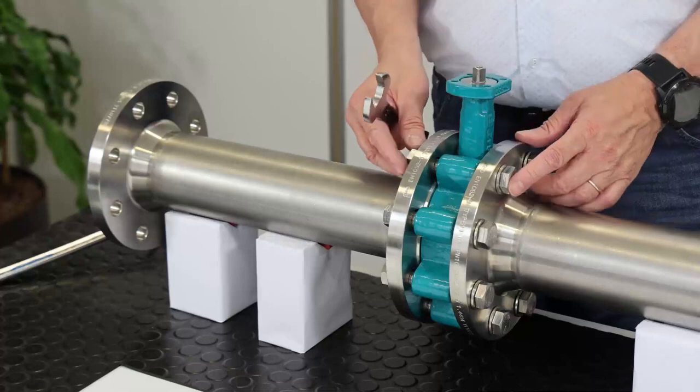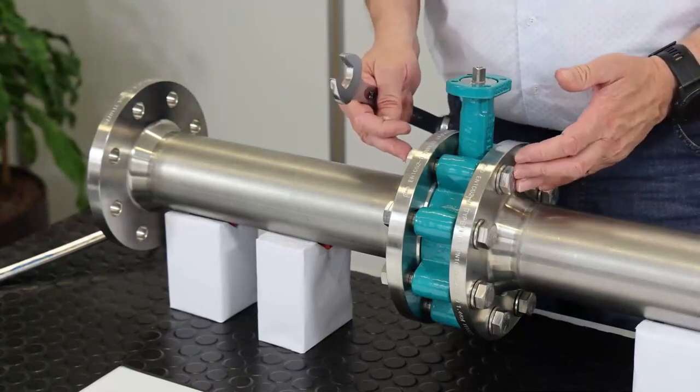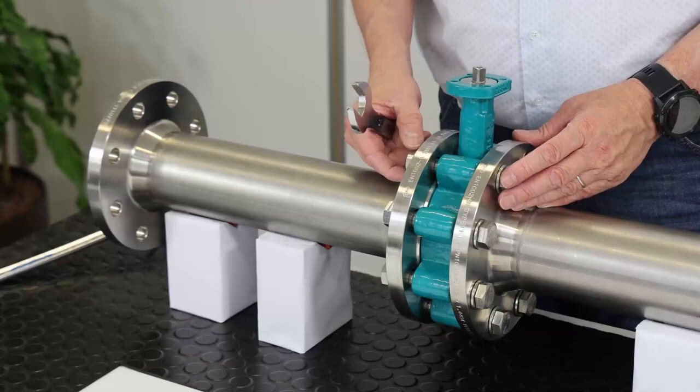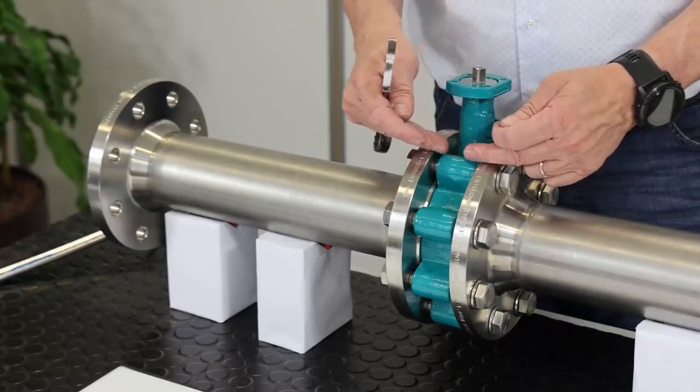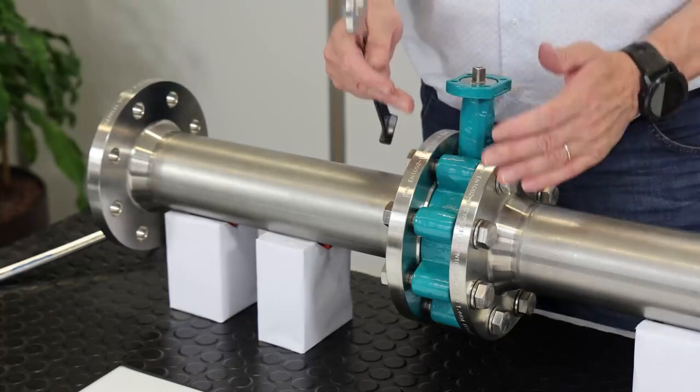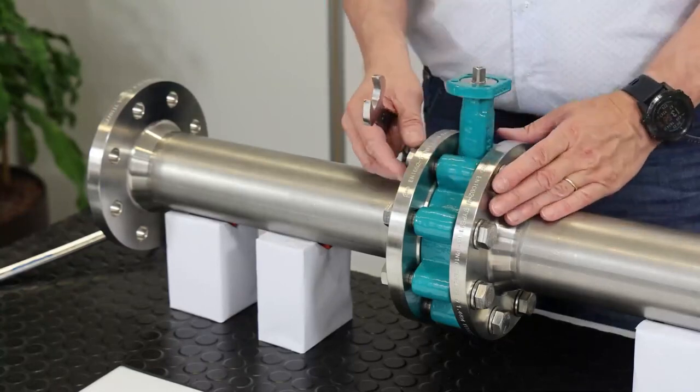It is important to consider the torque tables from the screw supplier when assembling the valve between flanges. If you tighten them too much, there is a risk to elongate the screws. This is important on the rubber lined butterfly valve.